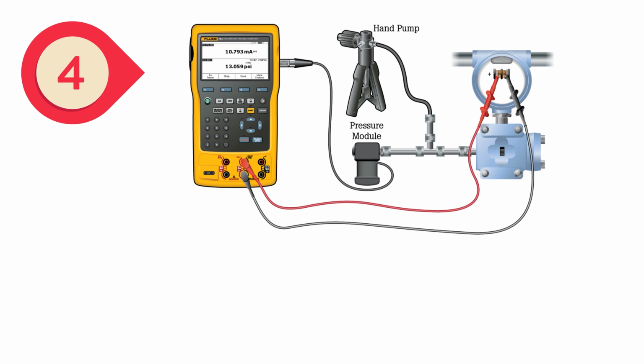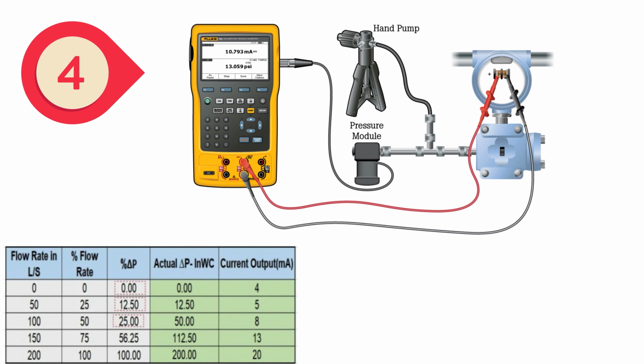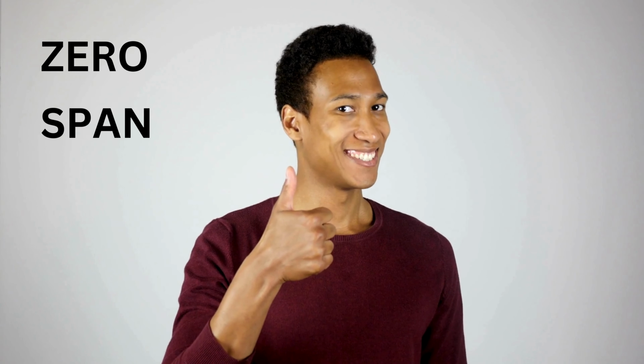Step 4. Verify and test. After making adjustments, check the transmitter's readings at several points across its range to ensure accuracy. Recalibrate if necessary, and ensure that the transmitter is functioning correctly before putting it back into service. And that's it. Zero and span adjustments are now done.